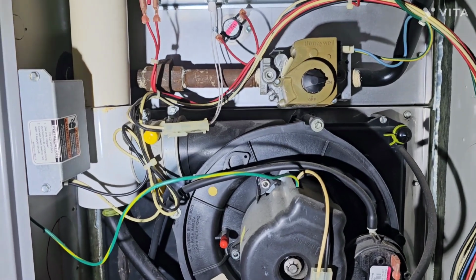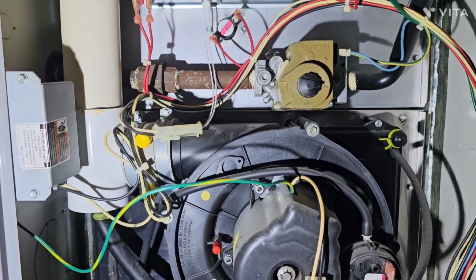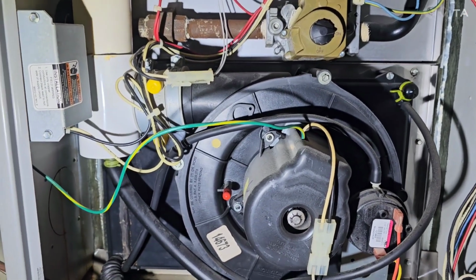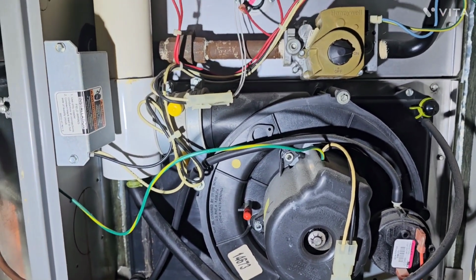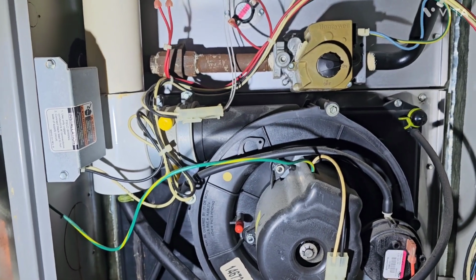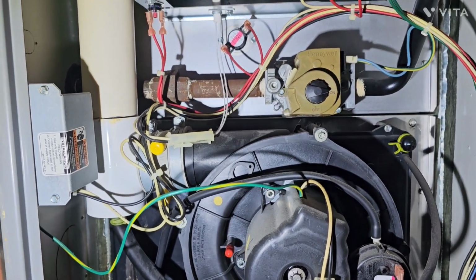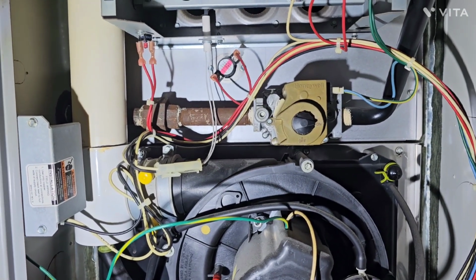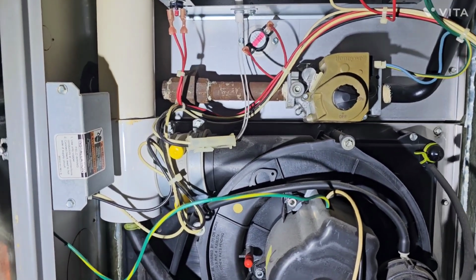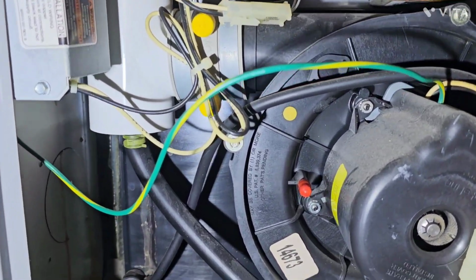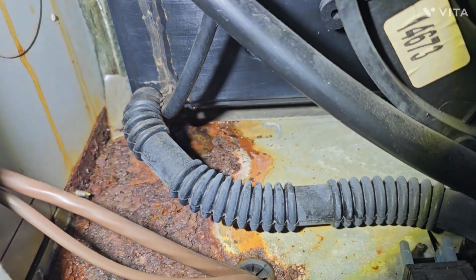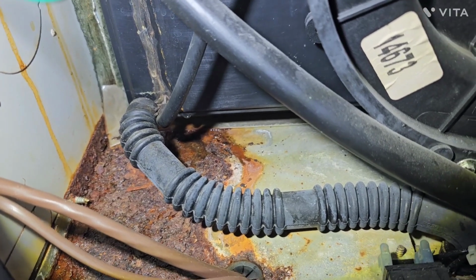When they're burning the fuel, under normal circumstances a furnace is going to burn about 80% of the fuel. In a modern day system, they transfer that heat around the furnace through combustion chambers and so on, and they get the last little bit of heat they can possibly get out of the system. What happens when you do that is you create condensate, and that condensate has to be dealt with. So they have drains and so on there, and you can see here the condensate's been dripping down and ending up in the bottom of the cabinet.